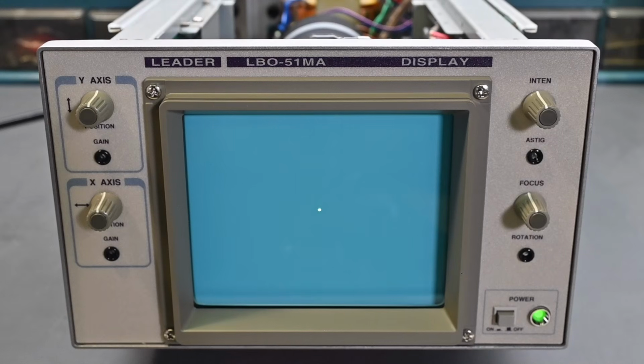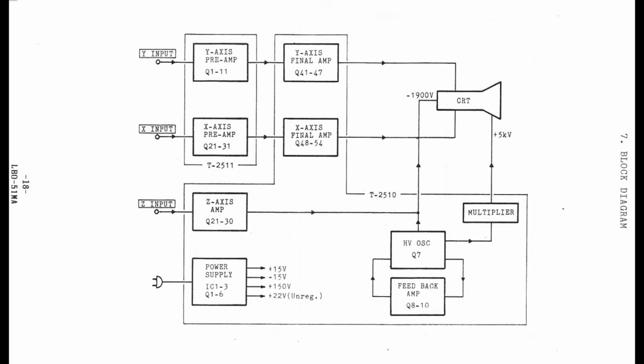So this XY display has the blue filter plate installed, so there are no graticule lines. There was a graticule plate optionally available with the standard 10 divisions for X and 8 divisions for Y. So the X and Y input range is 50 to 150 millivolts per division, DC to 3 megahertz, although the inputs can withstand up to 100 volts DC plus AC peak. So the full-scale deflection for the X-axis is 500 millivolts to 1.5 volts, and for Y it's 400 millivolts to 1.2 volts.